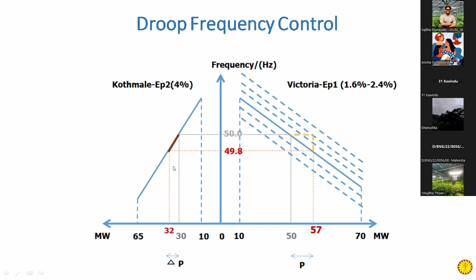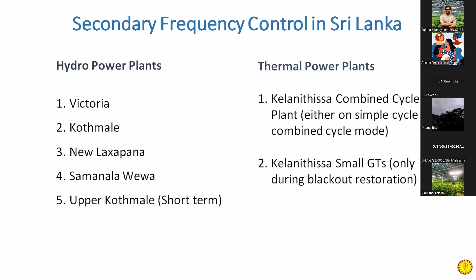In the other case, in the Kotmale Power Station, what happened? It also sees the same frequency drop. But as its droop is 4%, there's only 2 megawatt of difference. In other words, in the Kotmale Power Station, its governor tries to increase only 2 megawatt, while Victoria Power Station tries to increase 7 megawatt. Therefore, we call the Victoria Power Station the frequency controlling plant. The Victoria Power Station will increase by 7 megawatt and correct the frequency. So Kotmale Power Station is not required to increase, because the Victoria one is responding first. So these are the power plants that are capable of doing that frequency control, right?